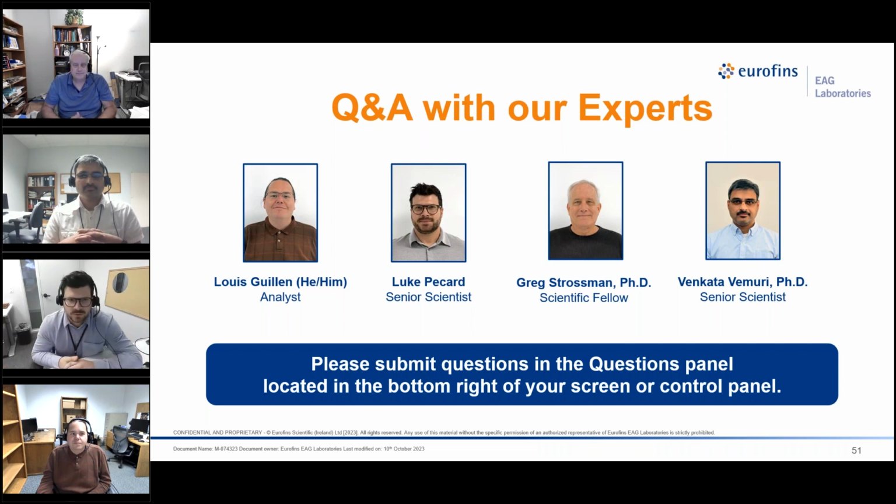Yeah, sure. So let's just give a little background here. XRF instruments come in 2 varieties based on the system for detecting the X-rays. The first being energy dispersive XRF or EDXRF. This type of XRF uses a solid state detector, which is going to provide fast simultaneous detection of the elements. EDXRF instruments have a high signal throughput, which makes it possible to operate at really small spot sizes, down to 5 micrometers or so in certain instruments, while also performing analysis fairly quickly.